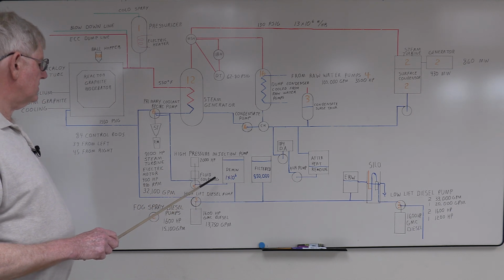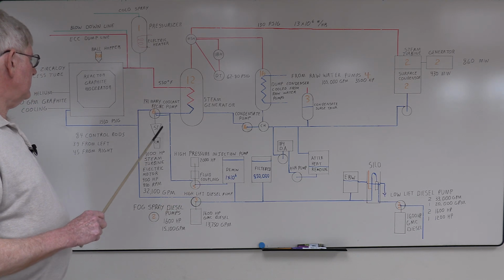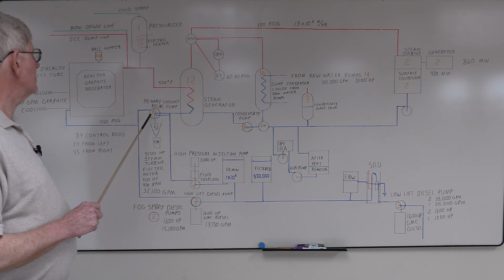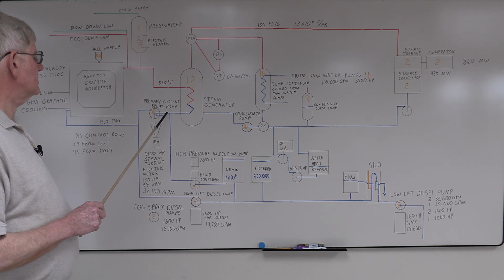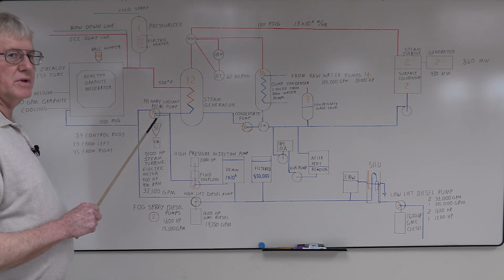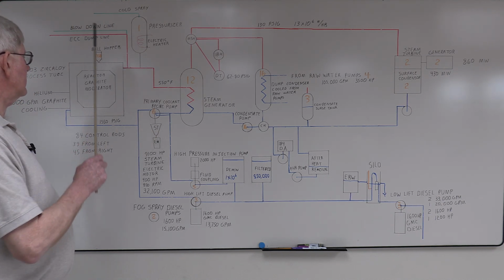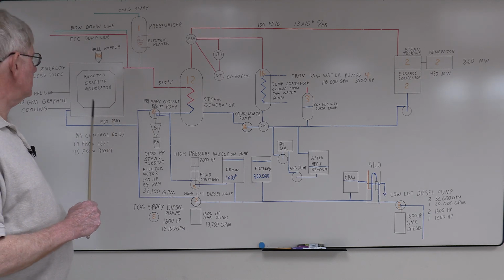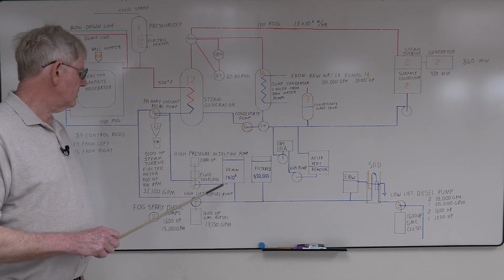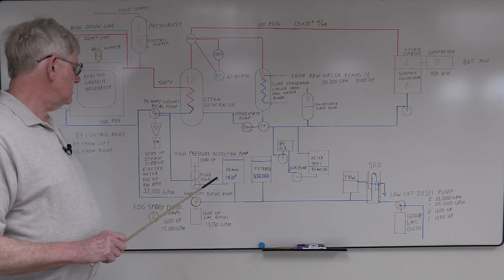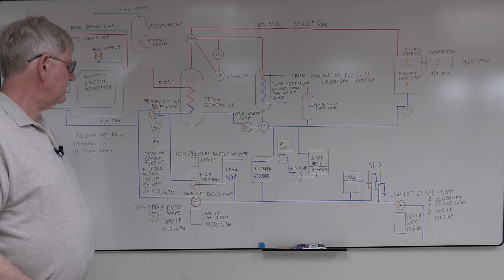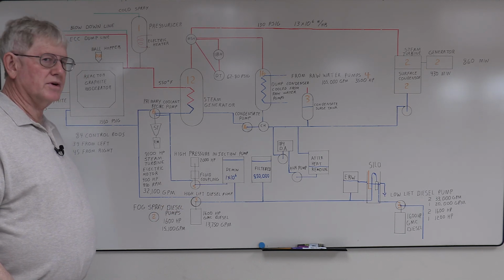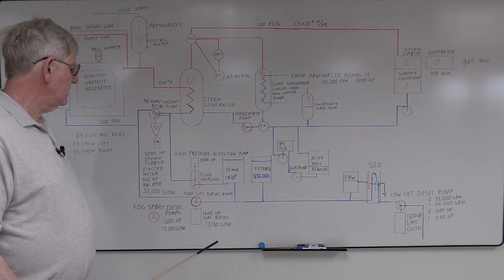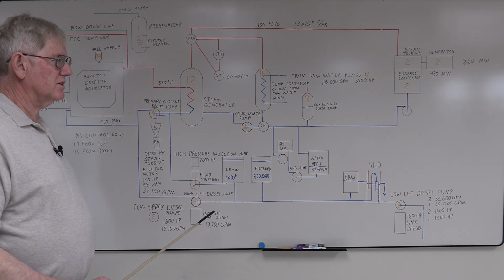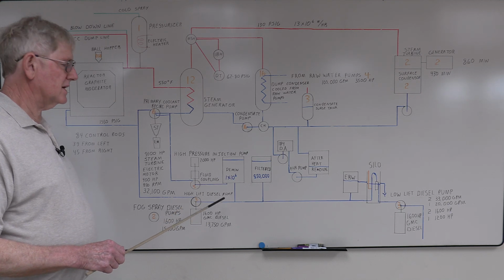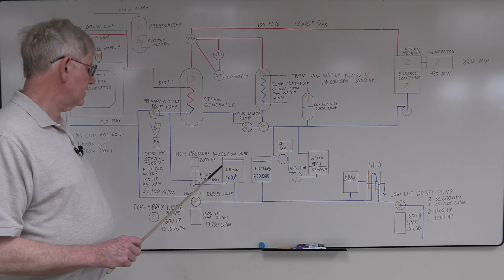They come off the demineralized water tank, and you'd feed seal water to the primary coolant pumps and also make up water to the primary loop. This water went through a heat exchanger first, off the blow down line, to heat up this water so you weren't injecting cold water back in. Demineralized water came out of a demineralizer plant using cation, anion resin. It was regenerated with sulfuric acid and sodium hydroxide, capable of putting out about 2,500 gallons a minute, probably almost 3,000 if you really needed the water.